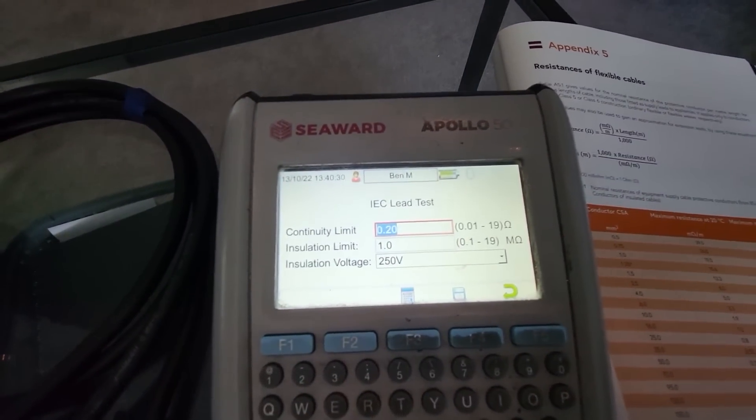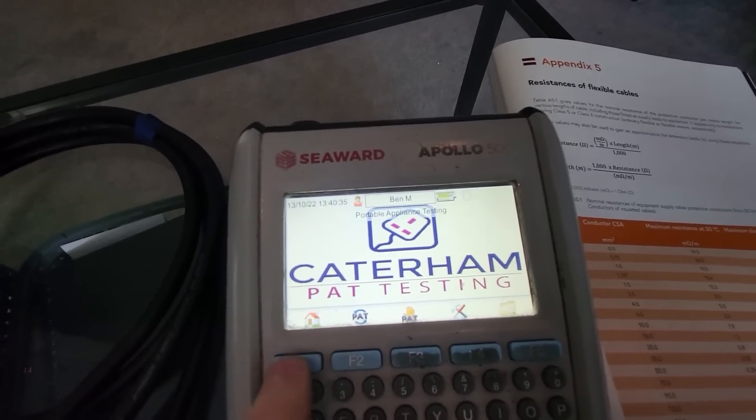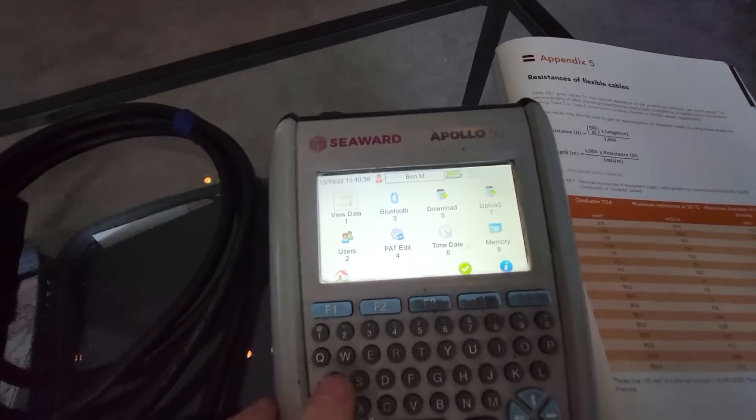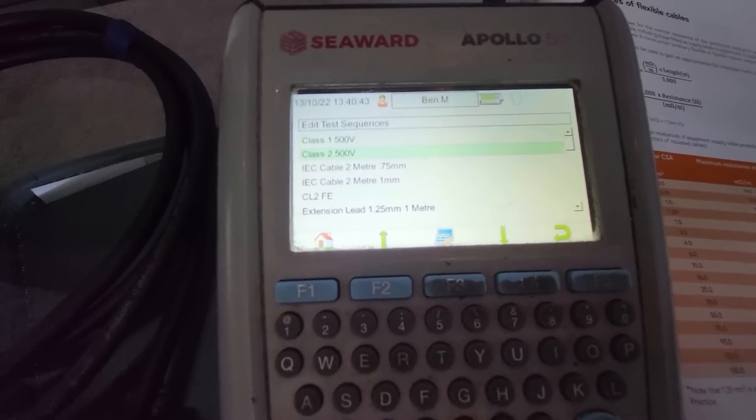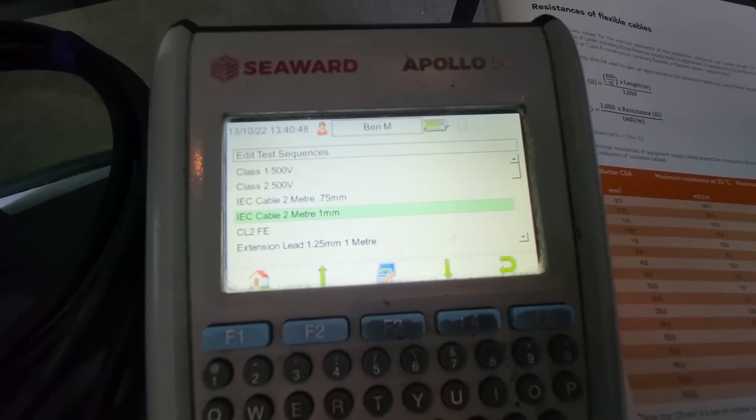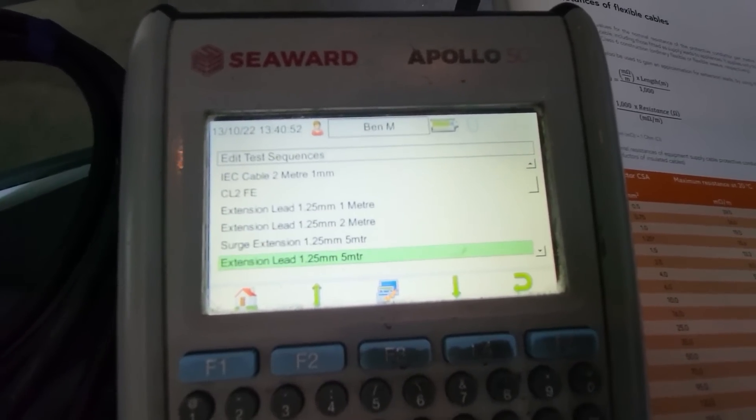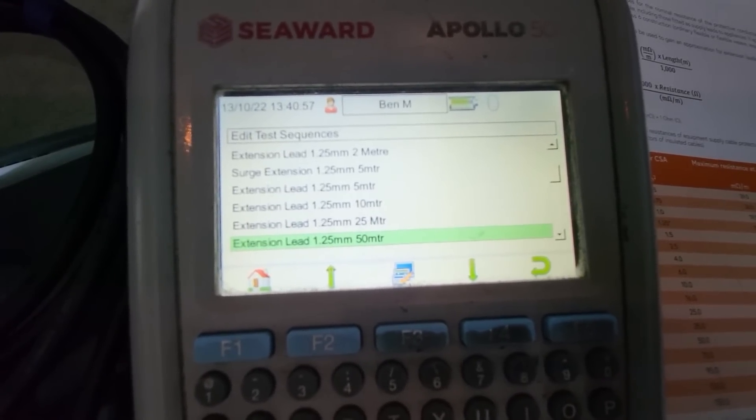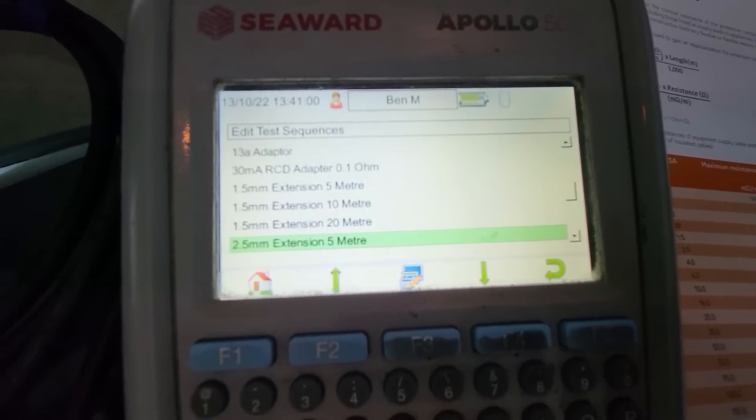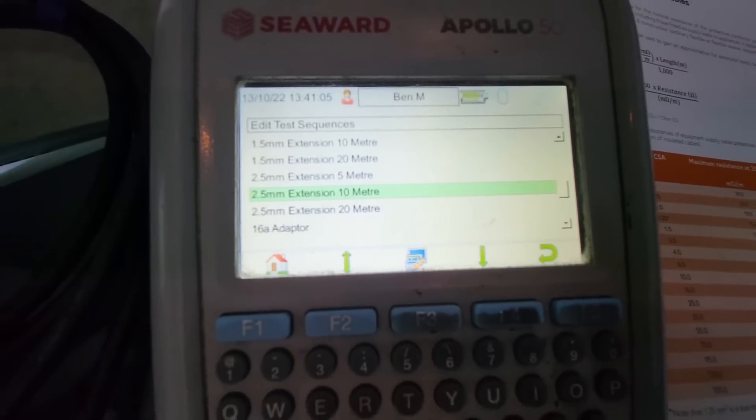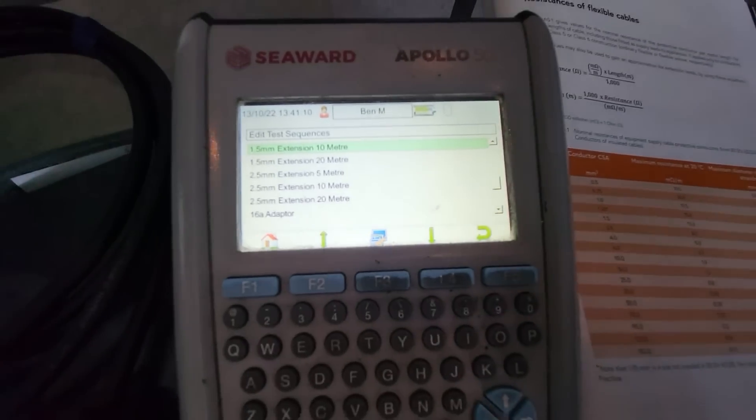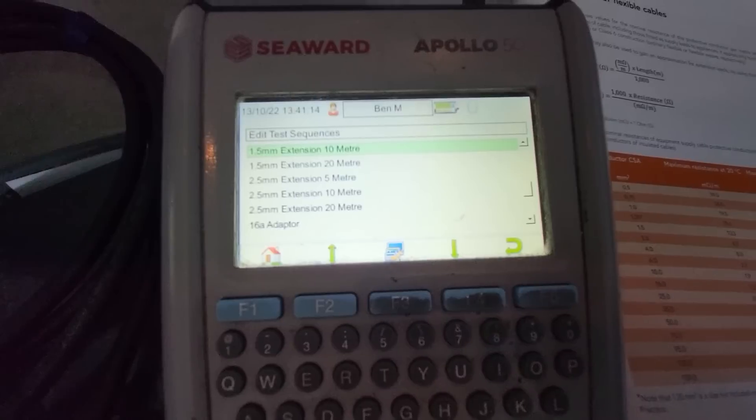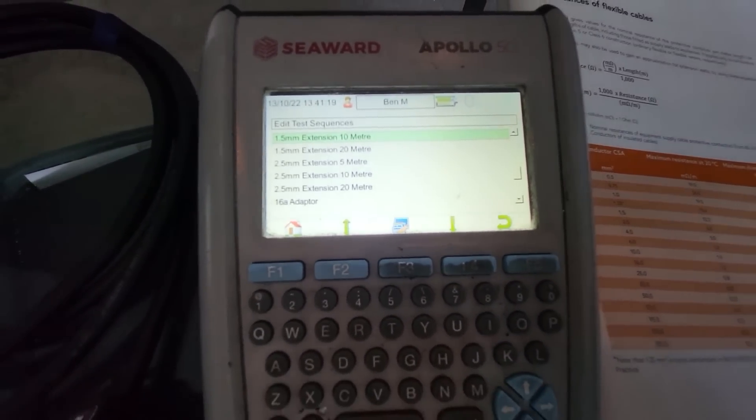Now, obviously, the difference with an Apollo, as I'll show you quickly here, if I just go into my settings here, as you'll well know, with an Apollo, and this is why they're so much better than the entry-level machines. Obviously, you can put in pre-programmed test sequences. So as you can see there, you can pop in extension lead, different lengths, different cable cross-sections. So I've got 1.25s at different lengths there. I've also got 1.5 and 2.5. So if you come across 110-volt cables at different lengths, obviously, they're all pre-programmed in, so you don't need to do the manual calculations. You just select the one nearest to the item you're testing, and it will obviously be pre-programmed and do it all for you.